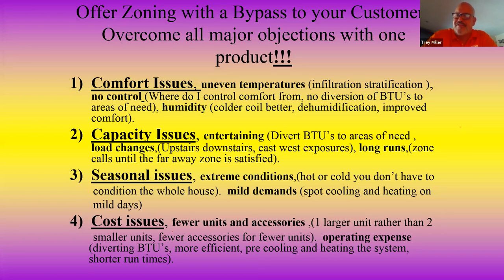So basically, if we have 15, 20 people over at our house, they're miserable. The nice thing is go to the sleeping area or go to the other zones, cut them off, divert the BTUs into that area. This allows you to entertain with comfort. Load changes, upstairs, downstairs, east-west exposures. How about long runs? You've got a 25-foot run and the rest of them are about 6, 8, 10 feet. That long run never gets satisfied. If I put a thermostat on the wall, and guys, that's one thing, I can solve any problem temperature-wise by just putting a thermostat in that area. It's going to continue to call until it's satisfied.